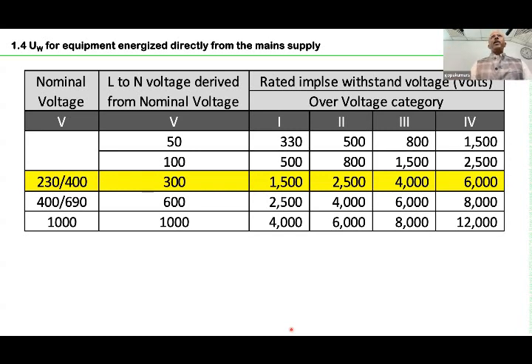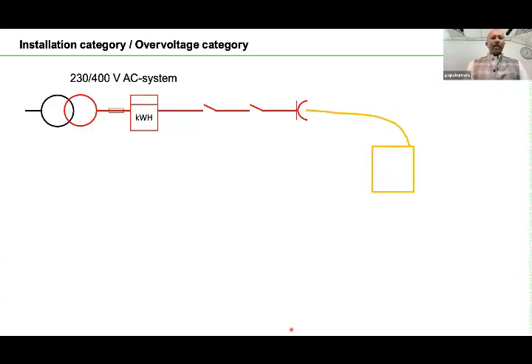So the first parameter to understand is to look at the manufacturer's catalog, especially for switchgear and so on, where you can find this parameter: the installation category or impulse voltage withstanding category. That is the first parameter to be looked into.